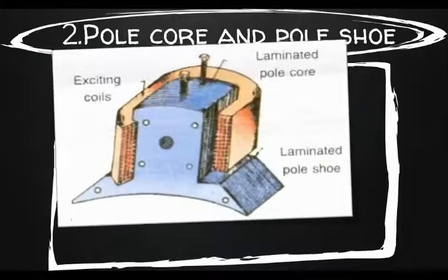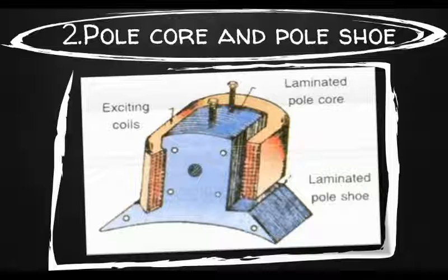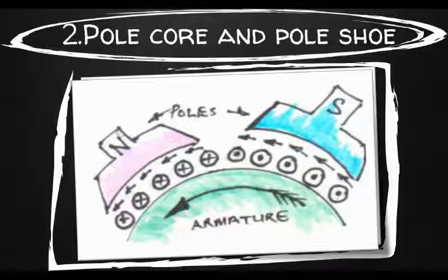Pole core and pole shoe: The field magnets consist of pole core and pole shoes. Pole core is usually of circular section and is used to carry the coils of insulating windings carrying the field circuit current. Pole cores are not usually laminated and are made up of cast steel. The pole shoe serves two purposes: they spread out the flux in the air gap and, being of larger cross section, reduce the reluctance of the magnetic path. They also support the exciting coils.